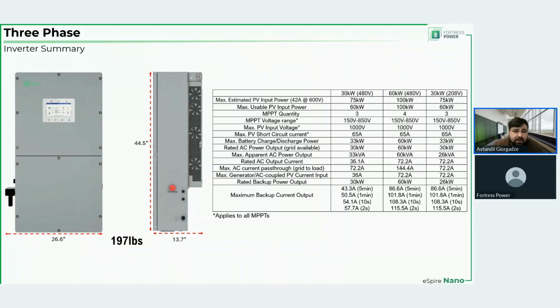So 43.3 amps compared to 36.1 for the 30 kilowatt 480 unit. That 43.3 is only for 5 minutes. It's not continuous. Very important to understand. That's why I gave the time ranges there for every single one of these values. So this is a slightly more in-depth overview of the inverter summary. You can find the complete datasheet on our website, which you're more than welcome to visit and go to the Nano page. Whatever new we have and whatever documents we release for the general public will end up there.